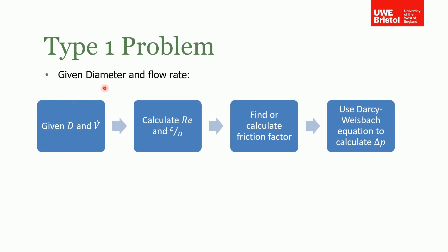Dealing with the Type 1 problem first — it's fairly straightforward. If we know the pipe diameter and the volumetric flow rate and all we need to do is calculate the pressure drop, then we can calculate the Reynolds number because we know the velocity from the volumetric flow rate and diameter. We can also calculate the relative pipe roughness, and from that we can calculate the friction factor from the Moody diagram or from the equations. Once we have that, we plug the values into the Darcy-Weisbach equation to calculate delta P — fairly straightforward.